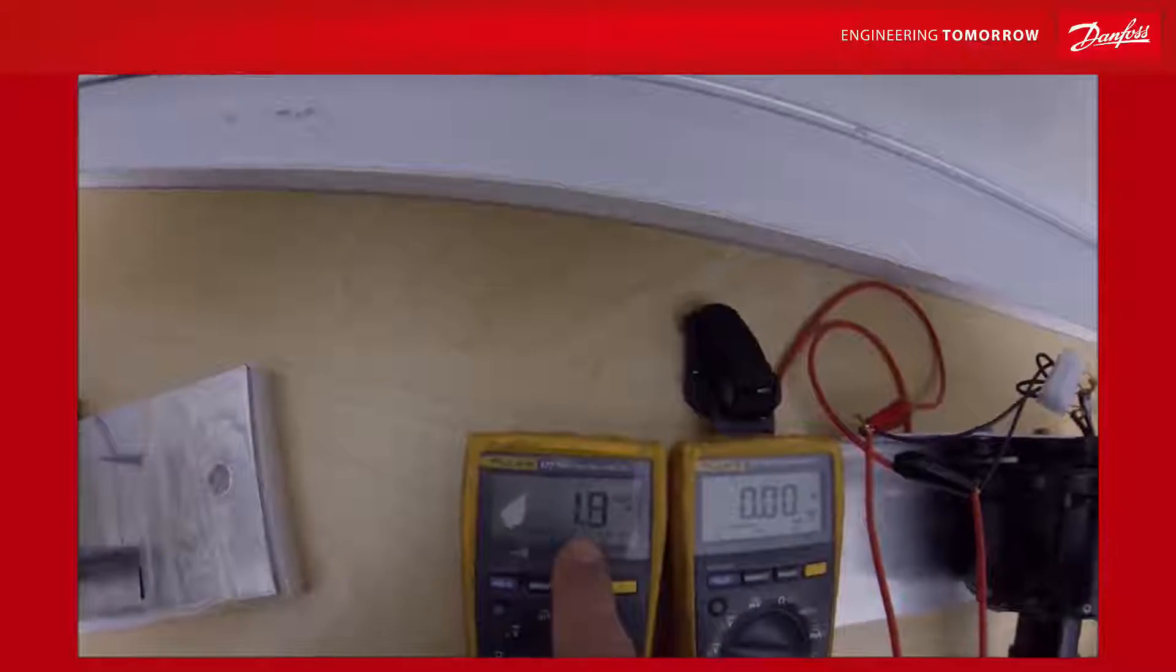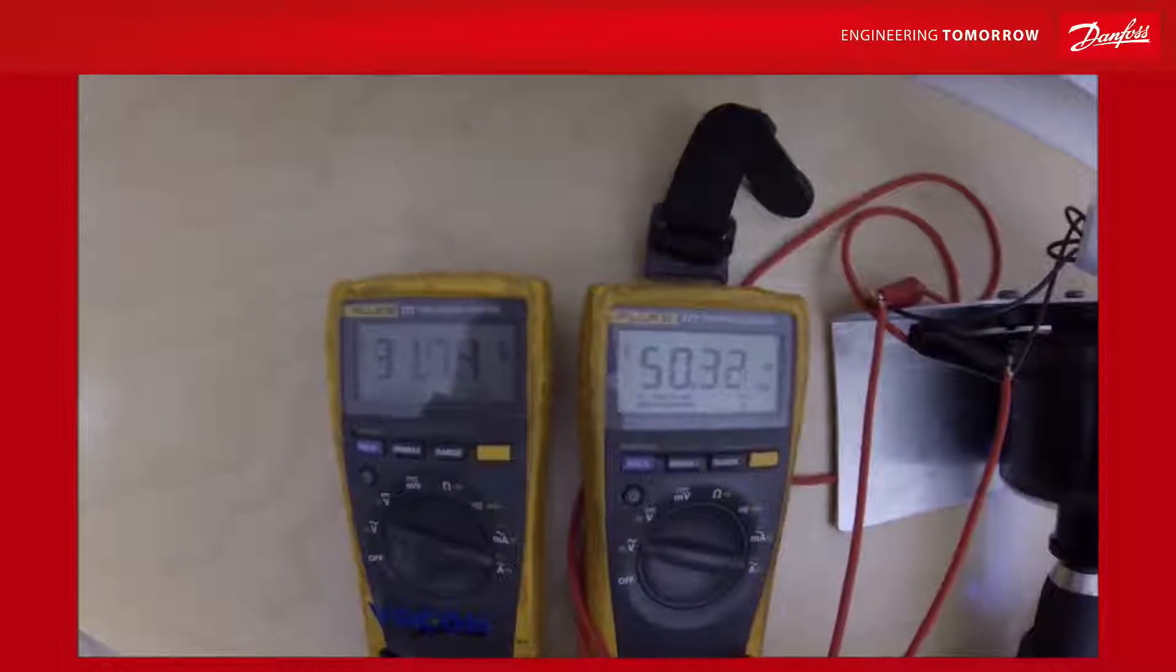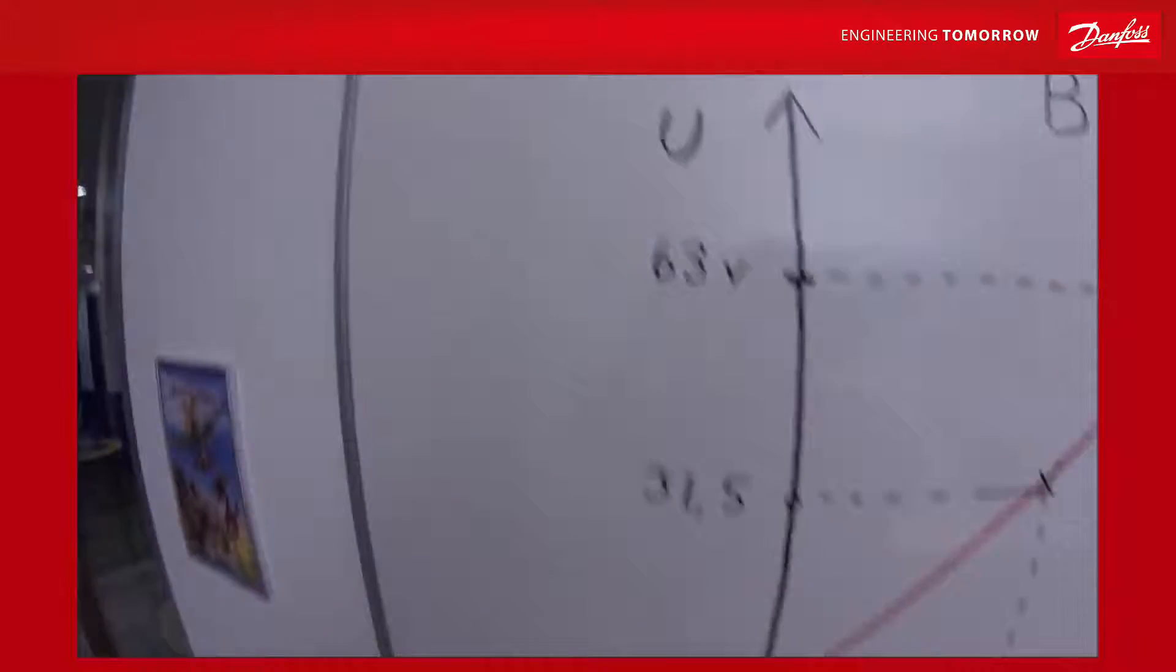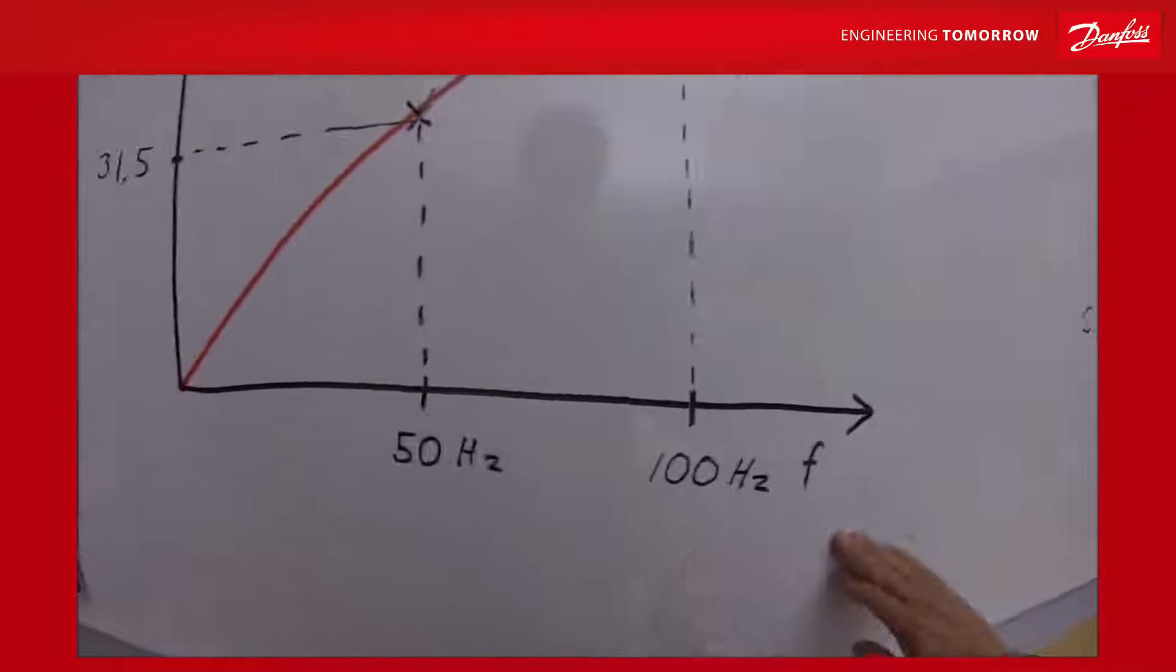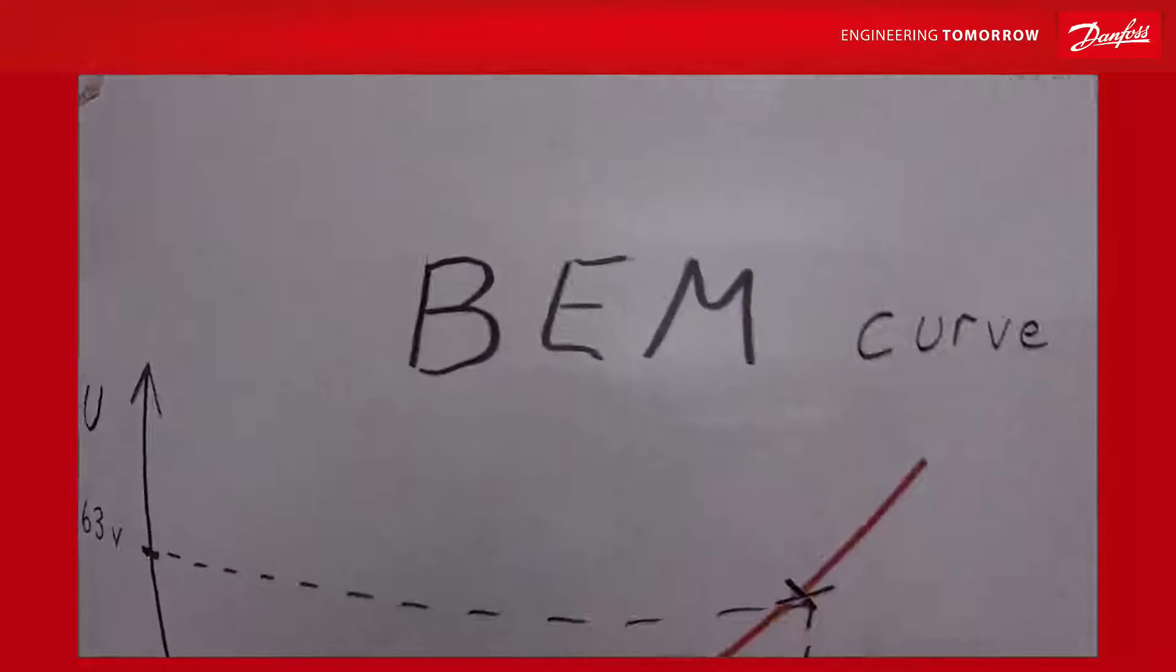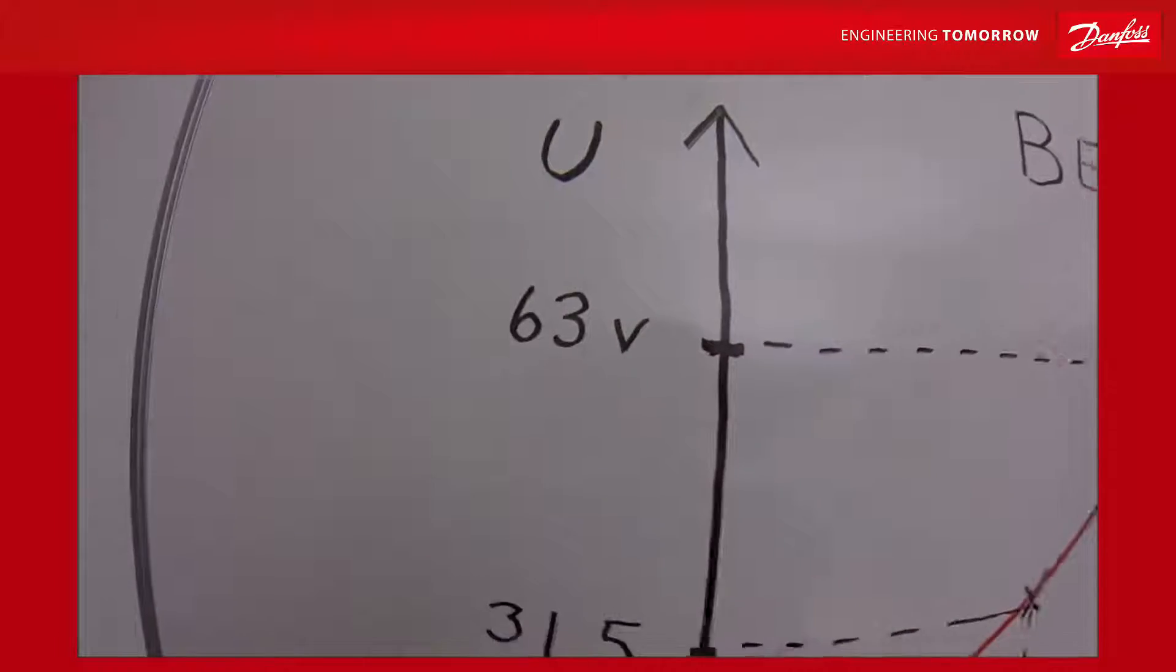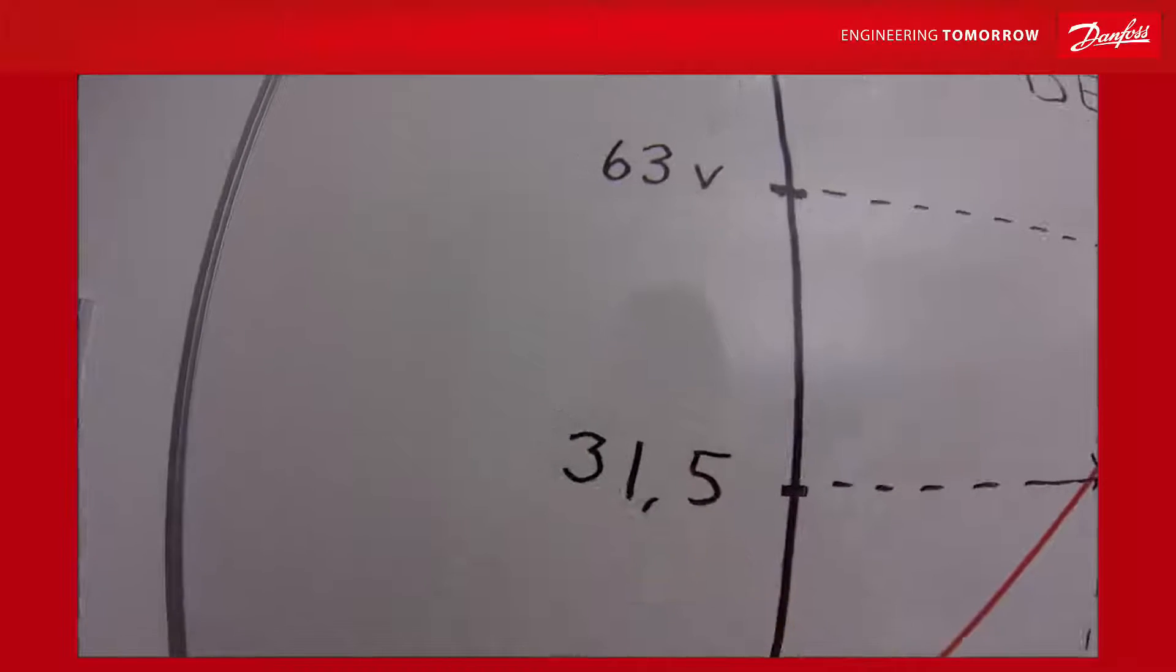And the relation between the voltage and the frequency is quite constant. The relation between the voltage on the output and the rotation speed of the shaft and then also the frequency have a constant relation called the back EMF curve. At 100 Hertz this specific generator produces 63 volts. Half the speed, 50 Hertz, it produces also half the voltage.